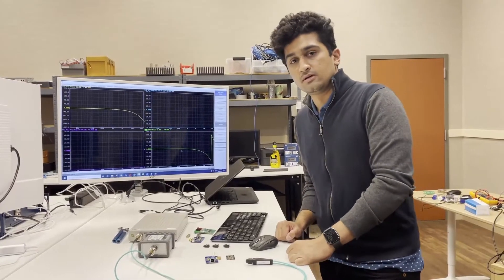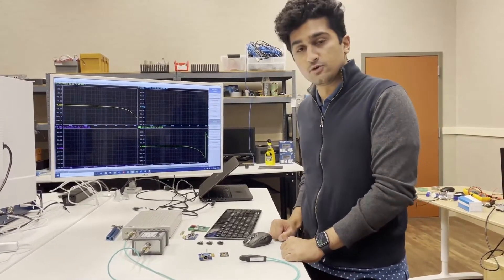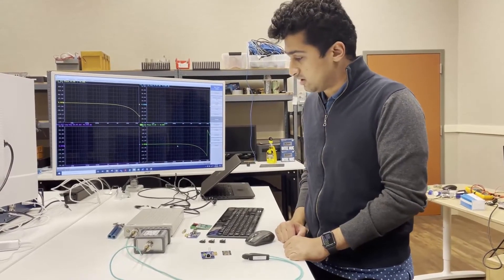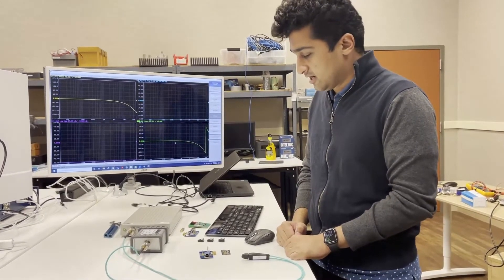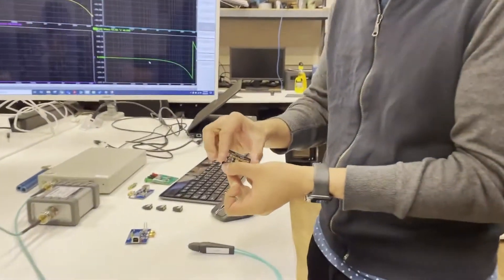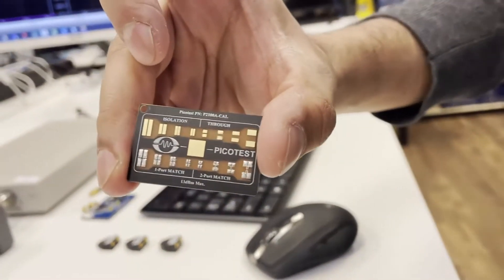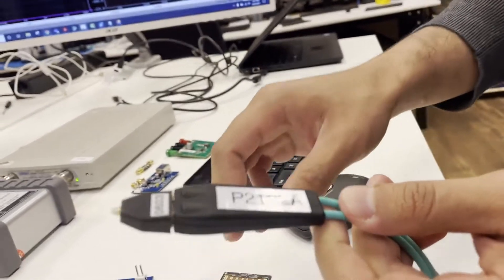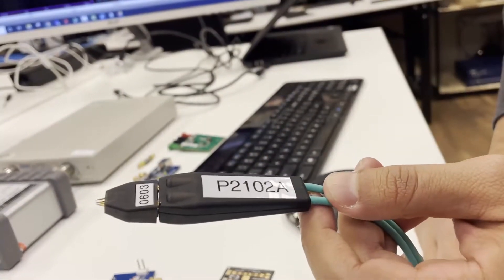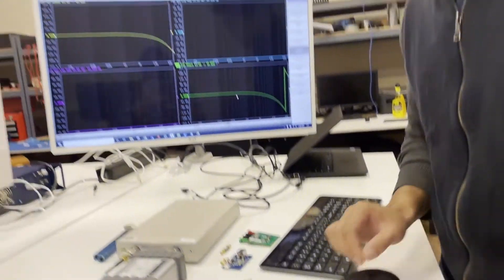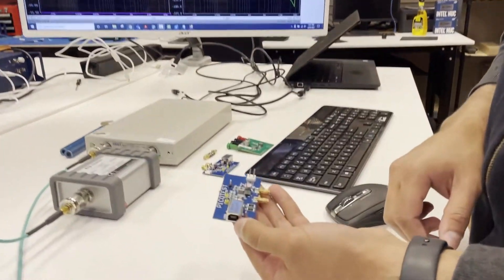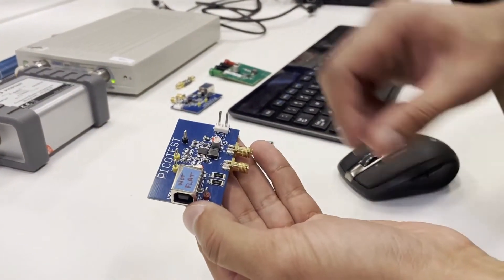Hi everyone, in this video let's look at how to perform full two-port calibration on a Copper Mountain Technologies two-port VNA using Picotest calibration substrate and the two-port probe, the P2102A. The measurement we will be doing is on the Picotest evaluation board and we'll be checking the measurements at the output.